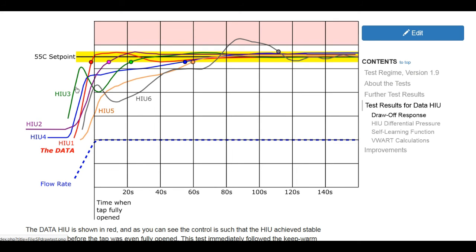Other HIUs, some of them perform better than others, with some achieving target within 20 seconds, within 30 seconds, others taking longer.